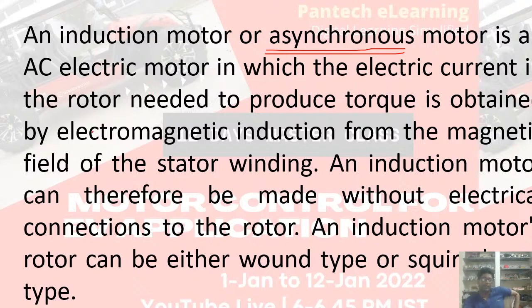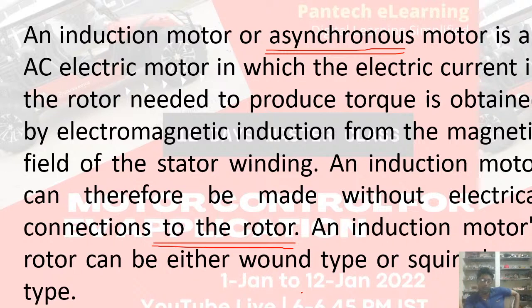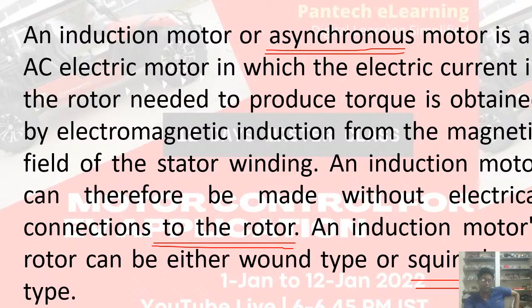The electric current in the rotor needed to produce torque is obtained by electromagnetic induction from the magnetic field of the stator winding. An induction motor can therefore be made without any electrical connection to the rotor — that's a great advantage. In a DC machine, you need to give some excitation to the rotor to make it a magnet, which is not required for an induction machine, making construction much simpler. The rotor can be either a squirrel cage type or a wound type, but most people prefer the squirrel cage type due to its construction simplicity and cost-effectiveness.